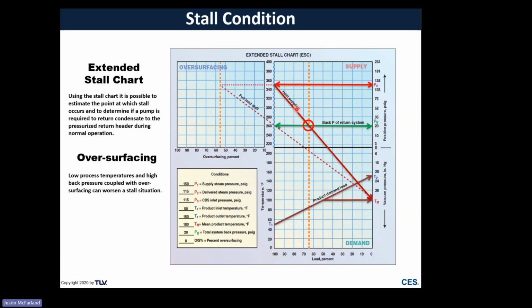So everything where your red line there is higher than the green line, we have a positive differential pressure. Steam trap's going to work. If that red line is below the green line, then it's a negative differential pressure scenario. So trap won't work. So you could say, all right, Justin, I'm going to tell you that my process heater never ever operates below this 63, 64% mark. Sure, okay, fine. Steam trap will work, not a problem. But if you're ever below that, steam trap's not going to work, and you're going to have all those suboptimal symptoms. Probably an operator is then going to have to open a drain and discharge condensate to the pad. So that's a problem. And we need to look at a different type of drainage solution than a steam trap alone.